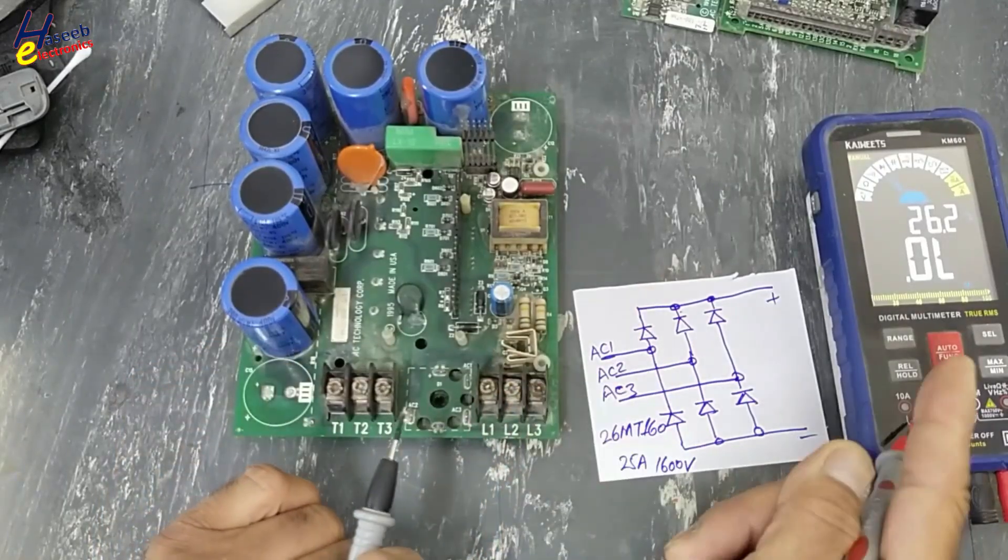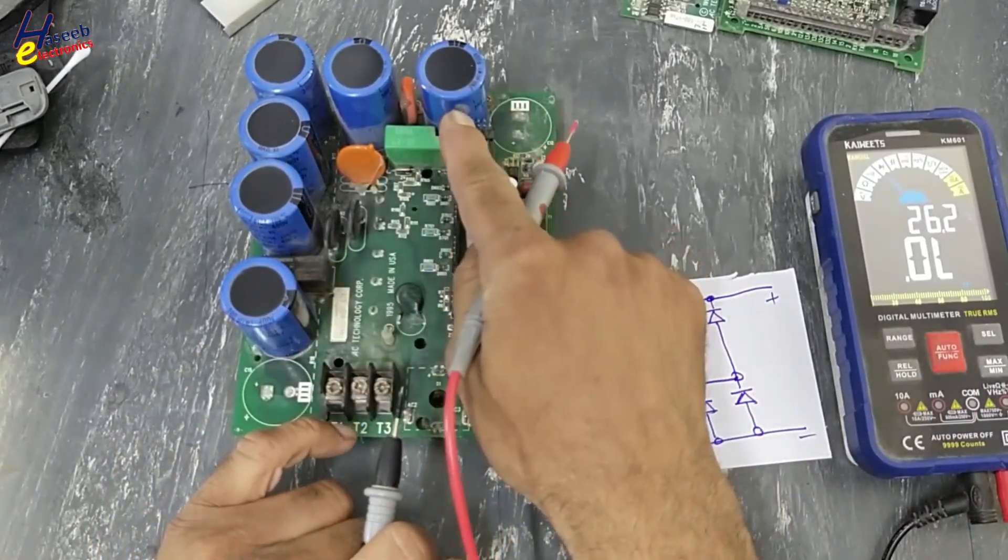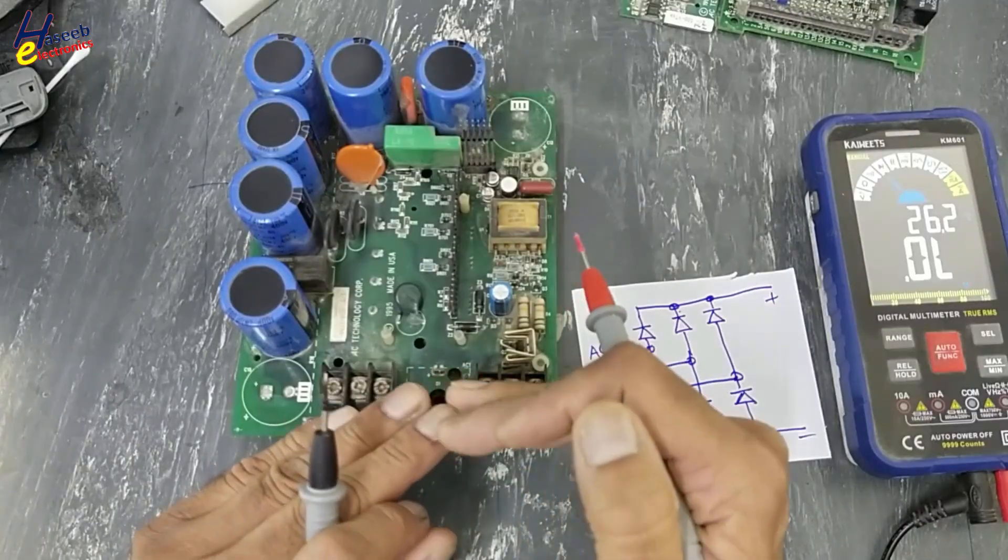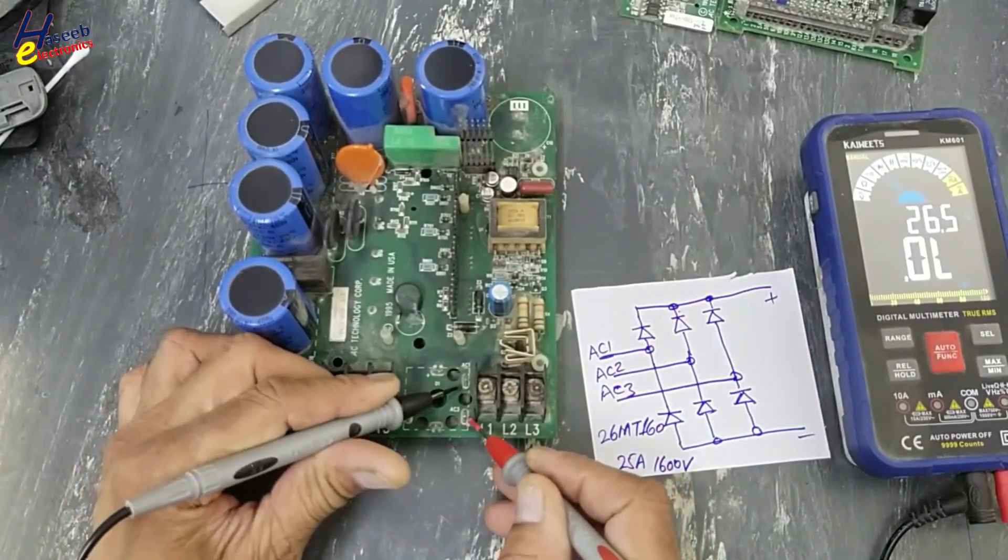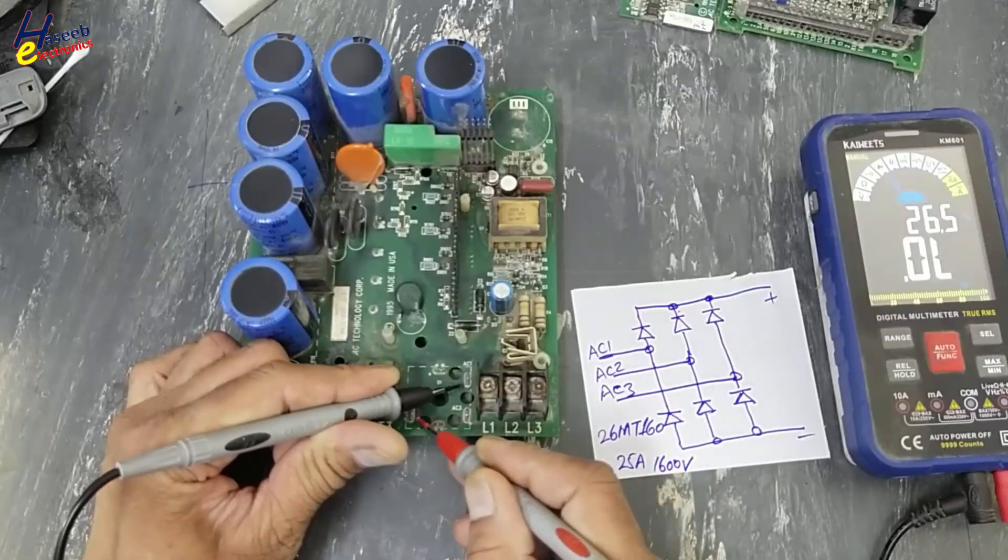That indication was due to these capacitors. Once these capacitors are charged, then it will show open circuit, OL, between all AC input terminals.